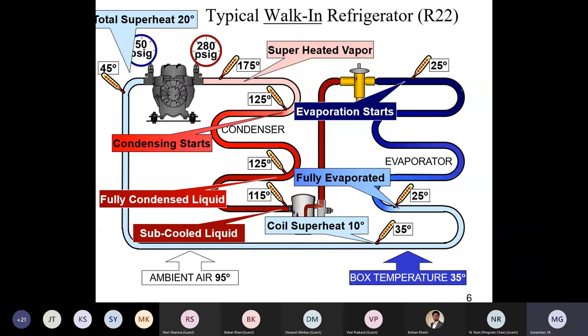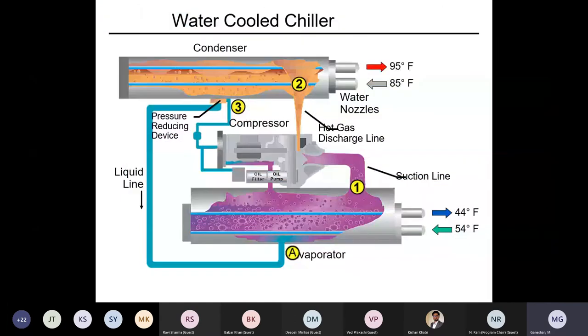Why? Because all our refrigeration compressors are designed to compress only vapor, no liquid. We will find out what will happen if liquid enters your compressors. This is where a system balance should take place. The metering and everything should function normally, then nothing will happen. Only when anything abnormal happens, everything becomes a problem. So let's see now. A similar thing is happening in a water cooled chiller. It will be the same thing.